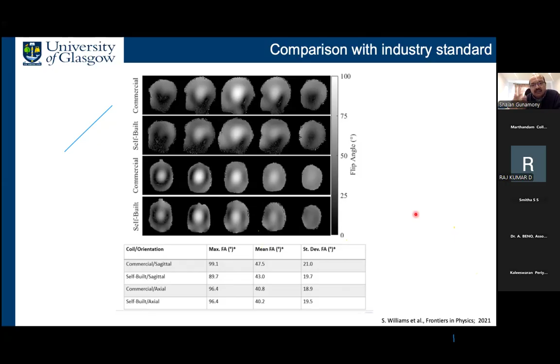Once we have all of this set up, we can scan this coil in the scanner. Here you see the comparison. This is the field produced by the coil in a phantom. We compare this commercial coil with the Glasgow head coil, and we see that it's quite comparable. In this case, on the transmit side, we are about 5% or so less. That's because we have these large cutouts, which reduced some field, but that is something we wanted to incorporate. So that was a compromise that we were willing to take.